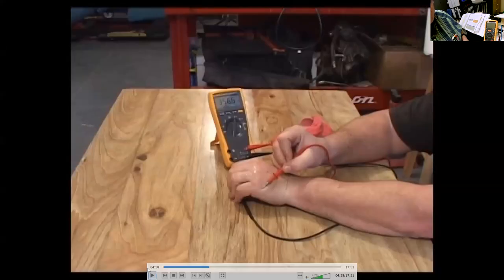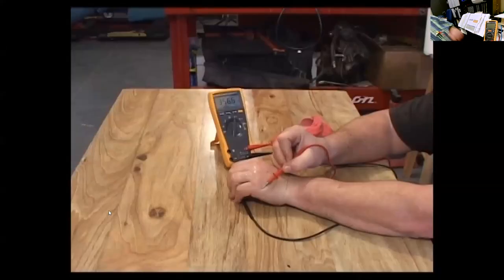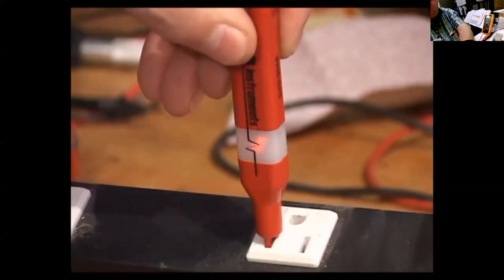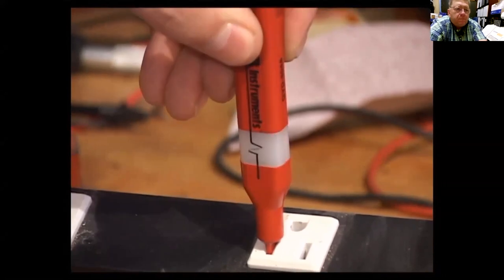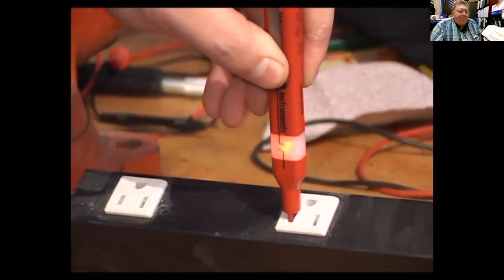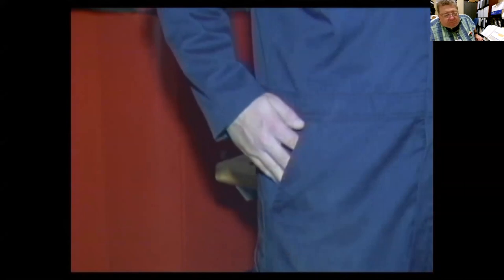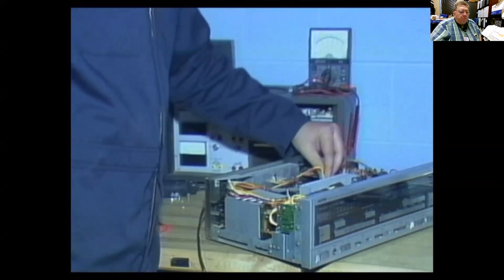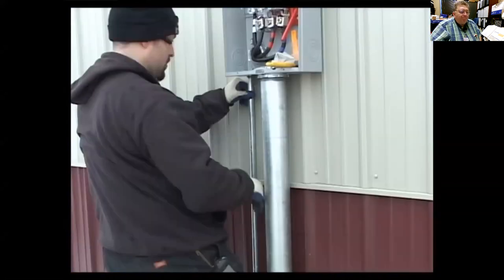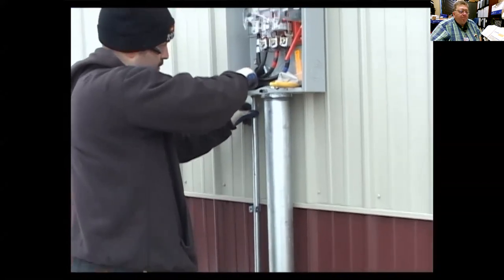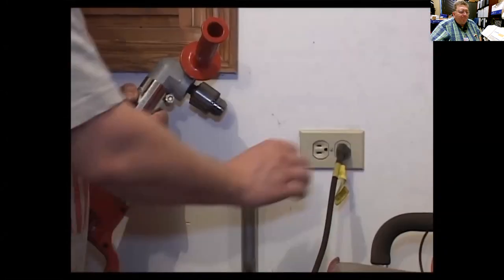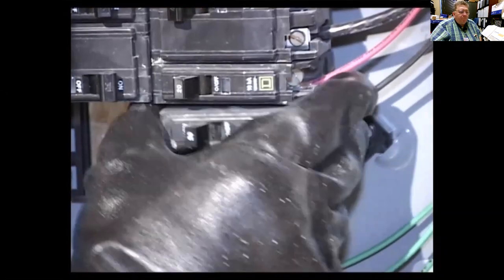Continuing the video: if in doubt about whether a circuit is dead, use a test light or multimeter to check for power. If you have to test a live circuit, use only one hand to reach near energized components. Current flowing between two hands can be more dangerous than current flowing through one hand down to your foot and to ground — current between two hands might flow across your chest causing heart stoppage.